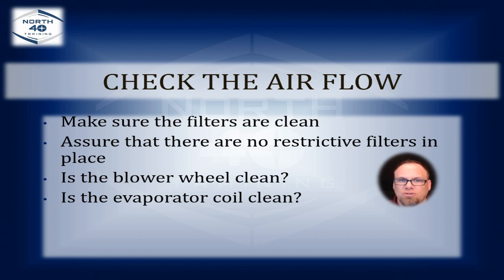And especially if you're using filters that are the least amount of restriction, which are those fiberglass filters. You know, that's what the manufacturer gets the efficiency ratings with. That's what gives you the best airflow. But that also, on the opposite side, is the least effective on the filtering side of things. But you can't take that into consideration because these furnaces were never meant to filter the air. They're meant to move the air so that we can create a comfort level through our heating and cooling system that's sufficient for the customers and efficient for the home.